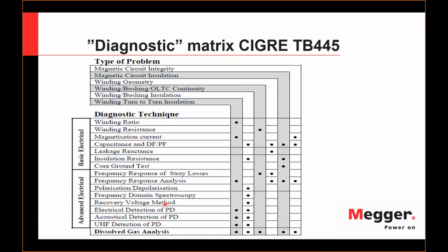PD, as the abbreviation is definitely well known to you, is partial discharge. It is also a very early symptom, a phenomenon that tells you that there is a process taking place inside the tank, and it might breach the complete insulation and lead from a partial to a total discharge or breakdown. So it is very useful to detect it at an early stage, to localize it, and maybe even to fix it. Condition assessment means looking at all of these properties, structuring them well, and deriving conclusions from all those findings. That was an example of a CIGRE view.